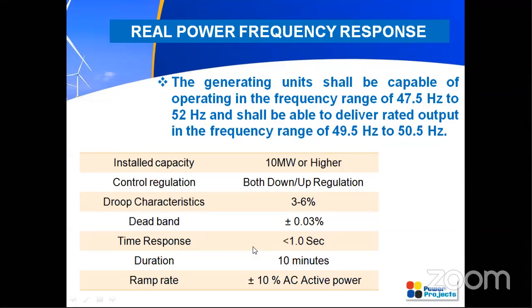I will stress this point once again. Whenever there is a frequency deviation that exceeds 0.3 hertz, your generating station should provide an immediate real power primary frequency response. The response should be at least 10%, and it should be given within 1 second. That is the main thing. From 10% it may vary up to 100% of its maximum active power capacity, but a minimum of 10% it has to supply, with an immediate response within 1 second. That is another condition regarding the real time frequency response. And the rate of change of active power should not exceed plus or minus 10%. So all these are the conditions regarding your real power frequency response, and all of them have to be satisfied.